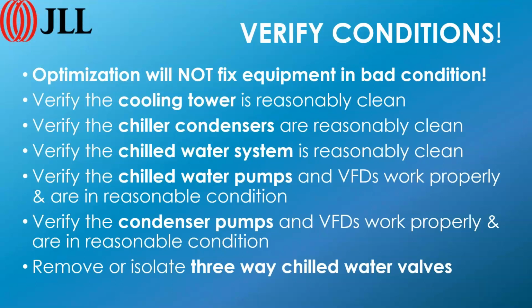Optimization is not going to fix equipment that is in bad condition. So we want to verify the cooling tower is reasonably clean and operates properly. If you've got busted up fill or spray heads that aren't working, optimization is not going to fix that problem. Same thing with chiller condensers. Doesn't have to be spotless, but reasonably clean. Chill water system, we want the chill water to be reasonably clean. Doesn't have to be spotless, but if it's black and thick and gooey, that's not a good thing. We've got to get that fixed up. We want the chill water pumps and the VFDs to be working properly. We're not going to put any additional strain on any of these devices. In fact, they're probably going to work less hard than they used to. But going through optimization and having equipment fail because it's not working properly is more complicated than it needs to be. So it's better to have the system in reasonably good condition before you start.